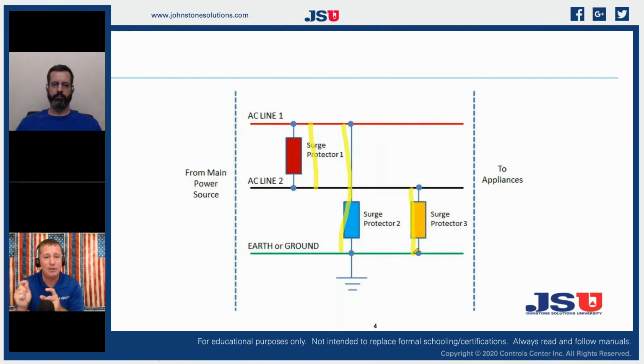So if we see that we have an elevated voltage coming across our AC line, either 1 or 2, we can redirect some of that voltage back down to earth or back down to ground and get it out of our circuit so that we can actually control voltage. So then if we add some capacitors into that thing, now we can control over voltages and under voltages by having an additional supply when it goes under. So we can use these circuits not just for surge protection alone, but we can use these for controlling our total supply of power. We can use these to help modulate our incoming voltage. We can control the peak and we control the valley, and we can make it a more neutral platform for our voltage. So we're actually using these as voltage conditioners as well.